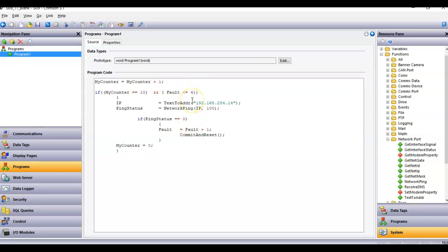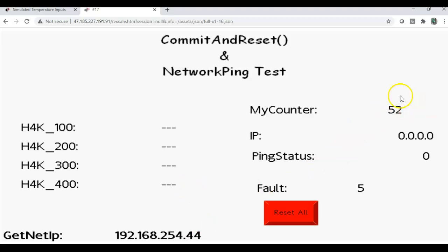Now that it's past that, what I'm saying is that this thing has done 4, actually 5, consecutive tests here. And rather than keep this cycling over and over again, I don't run this code anymore once this fault number is greater than 4. So that explains why this counter is just going to keep counting up forever. And you see how these are dashed lines here?